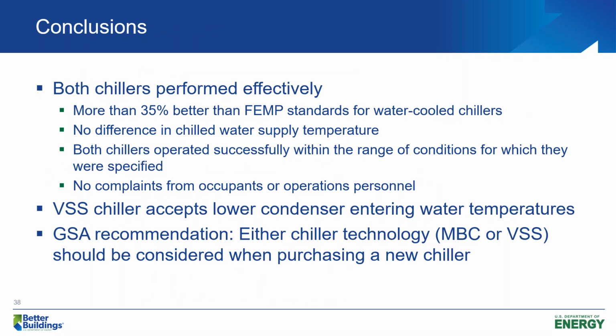So in conclusion, both chillers performed very well. As I said earlier, they're about 35% lower than the Federal Energy Management Program standard for water-cooled chillers. Both chillers provided excellent service to the building and chilled water supply temperature. They both had similar maintenance, basically no maintenance challenges during the demonstration period. The operations personnel liked both chillers. They both worked well.